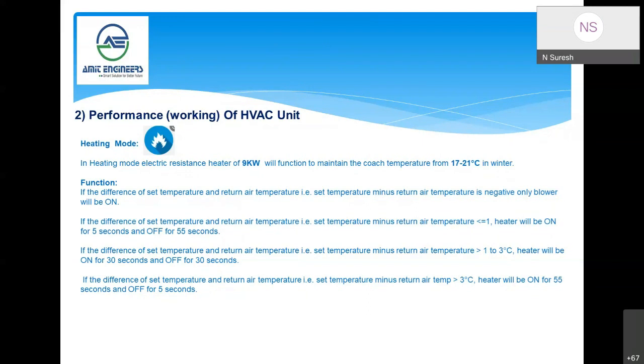This is again the function of the heater. If the set temperature minus return air temperature is less than or equal to 1, the heater will be on for 5 seconds and off for 55 seconds. If the difference between set temperature and return temperature is greater than or equal to 1 up to 3 degrees Celsius, the heater will be on for 30 seconds and off for 30 seconds. If the temperature difference is more than 3 degrees, the heater will be on for 55 seconds and off for 5 seconds. This is how the logic is defined.